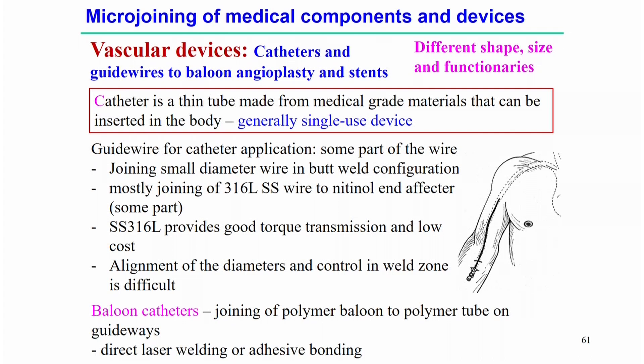For single-use devices, high-cost nickel-titanium alloy can be used. Sometimes it is necessary to replace part of the nickel-titanium wire or tube with a stainless steel tube, which is a cost-effective methodology. In that case, it is necessary to join the stainless steel tube or wire to the nickel-titanium alloy. For guide wires in catheter applications, some part of the wire may be joined as a small-diameter wire in butt weld configuration.